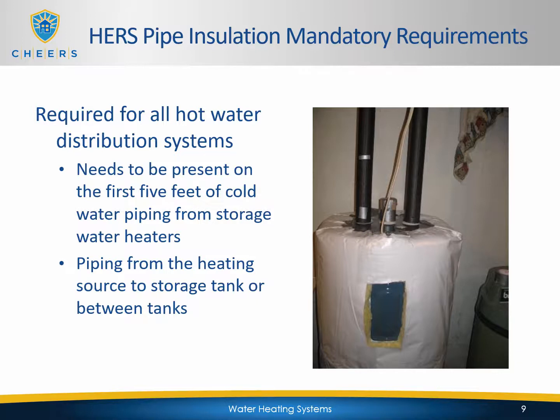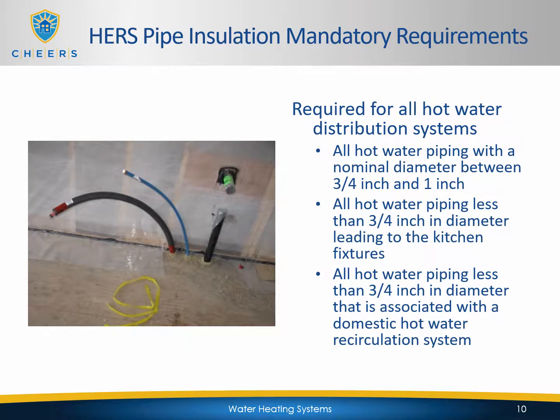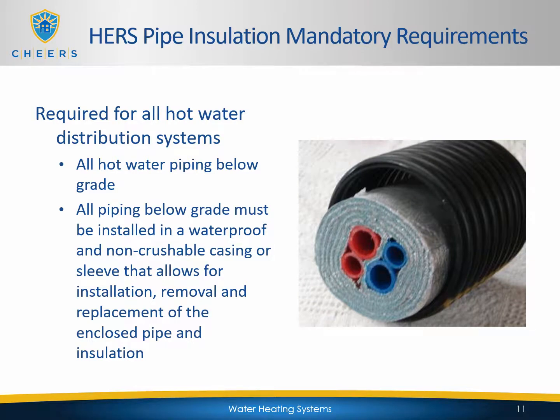Insulation is to be present on the first 5 feet of hot and cold water piping from storage water heaters. All piping from the water heater to the kitchen sinks and dishwashers has to be insulated. Also, all non-recirculating hot water piping of 3/4 of an inch diameter or greater. All hot water piping below grade has to be insulated.